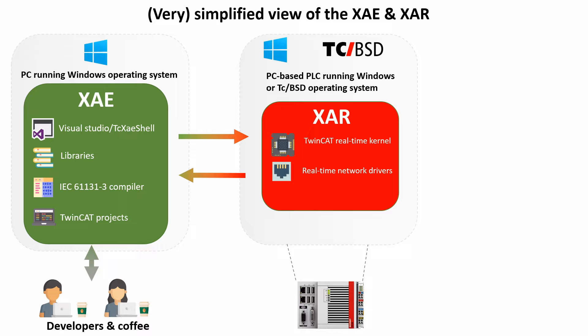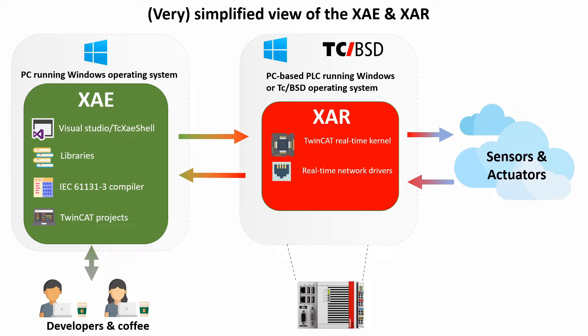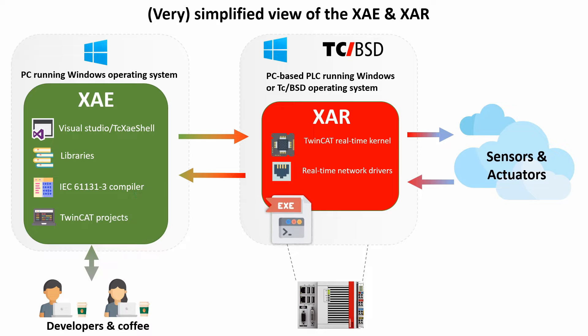Through fieldbus interfaces, TwinCAT can communicate with various sensors such as temperature, pressure, and position sensors, and it can also actuate actuators such as relays, valves, and electric motors. When you have successfully compiled a TwinCAT 3 project on your XAE development machine, it will create an executable binary. Through the integrated development environment, we can transfer this program to the XAR and execute it so that it's running in the real-time environment of TwinCAT 3.